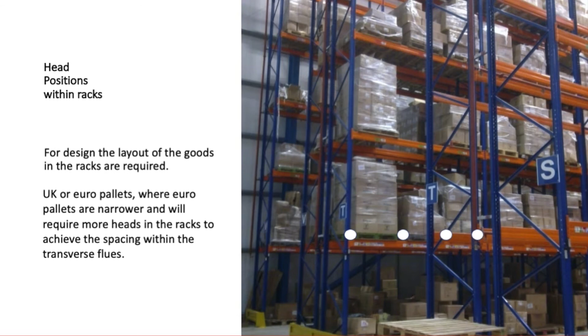When you look to hydraulically calculate systems, because pipe work is hydraulically calculated, it's not pre-calculated, so we have to actually work it out. When you're working out the amount of heads operating in the racks, it's 3 levels of pipe work in a rack. Now, if the aisle between the racks is over 2.4, which gives you that fire break, that's the same as we've got in block storage, you only need to calculate on 1 rack. So that'll be 3 heads and 3 levels, 9 heads operating. Okay.